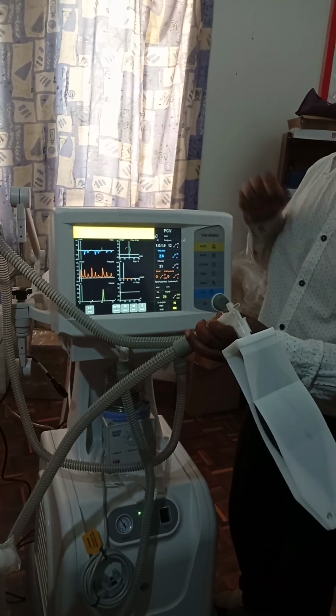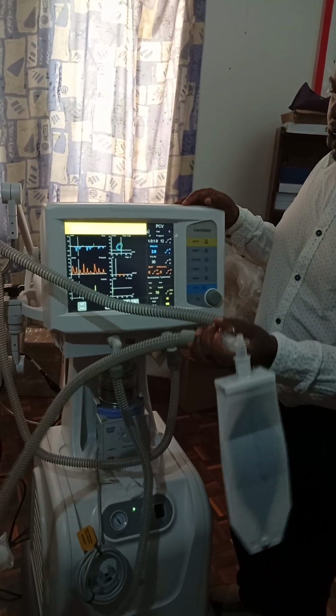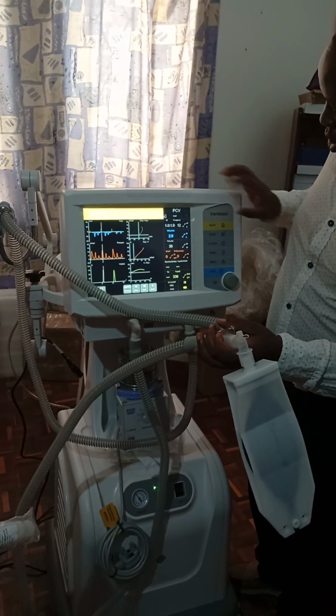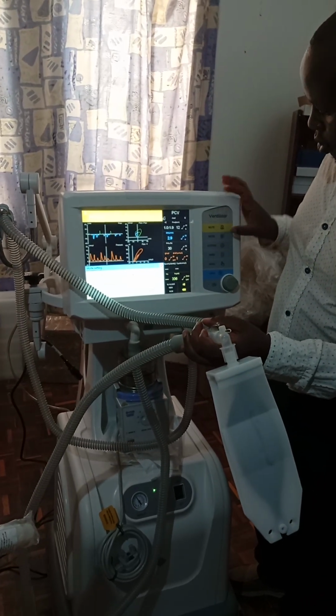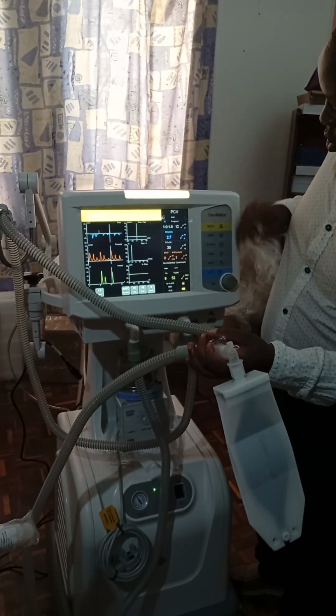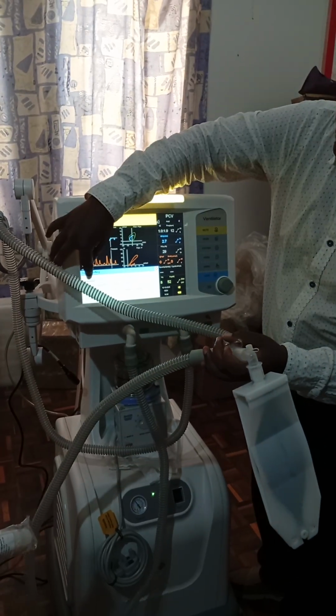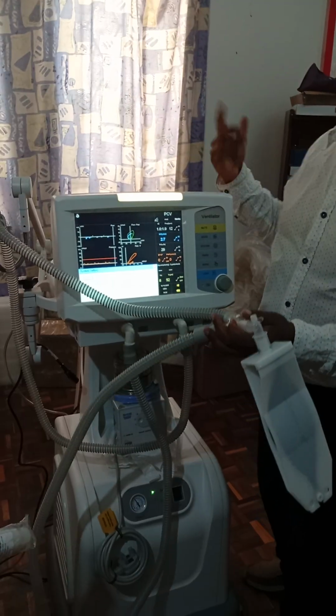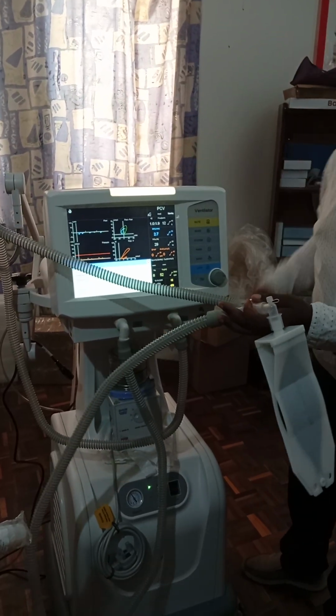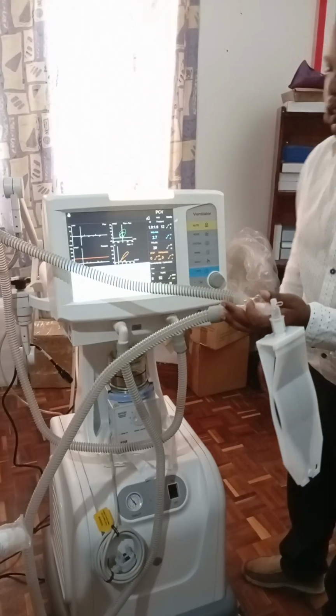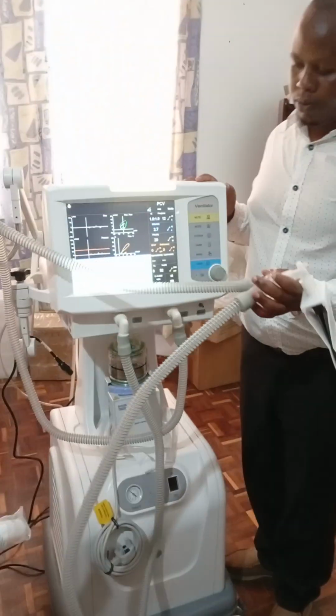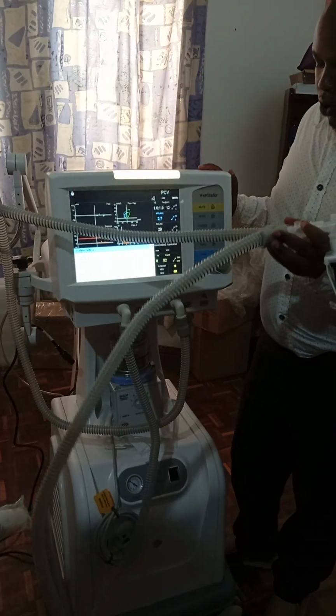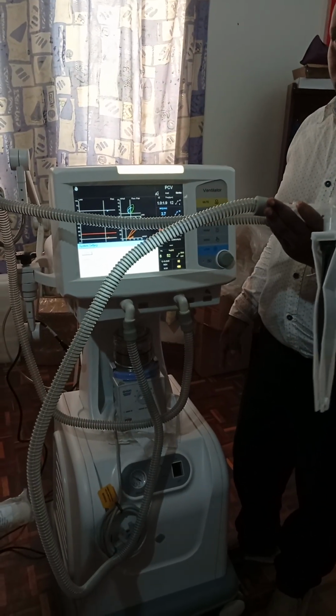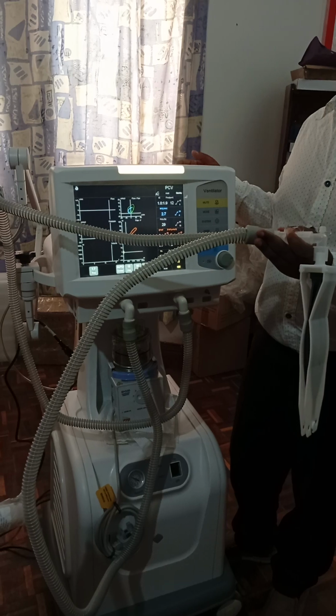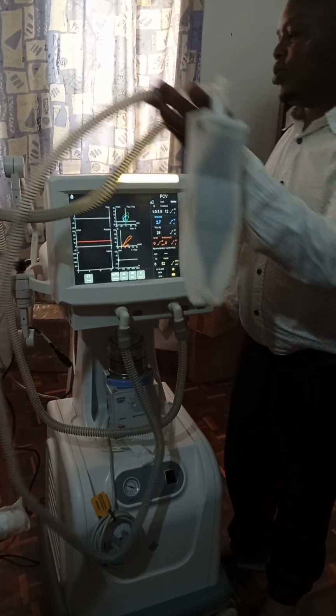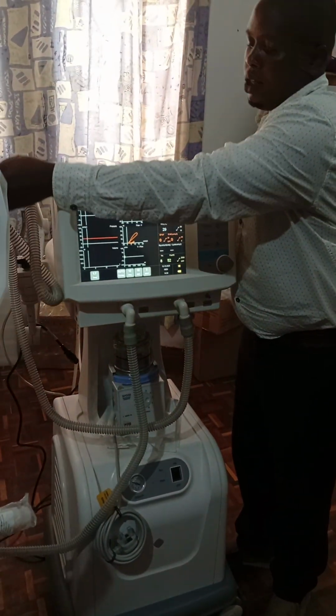So that's how it will be behaving. Once you confirm everything is okay, you can just come, press on the system, and you select standby. Then you will stop the ventilation. Then you can switch off this compressor. Now you see, when you are using this compressor, you'll be having a lot of noise. But if you are using the medical air, you'll not be having that kind of noise.